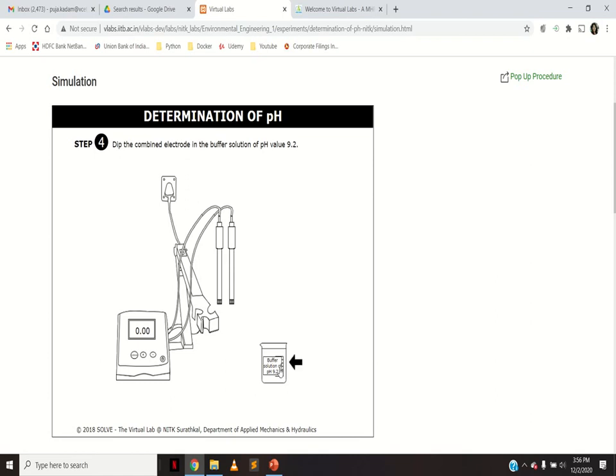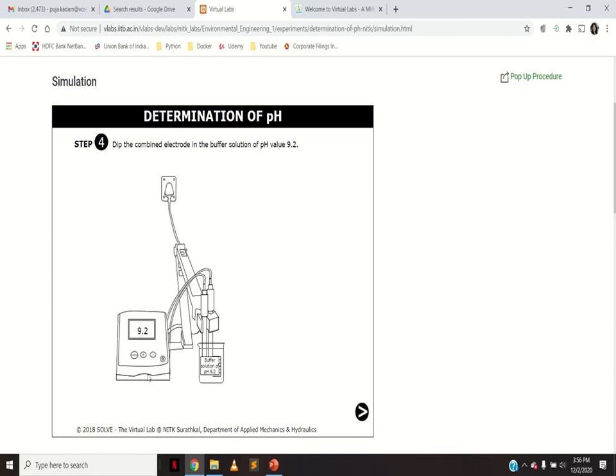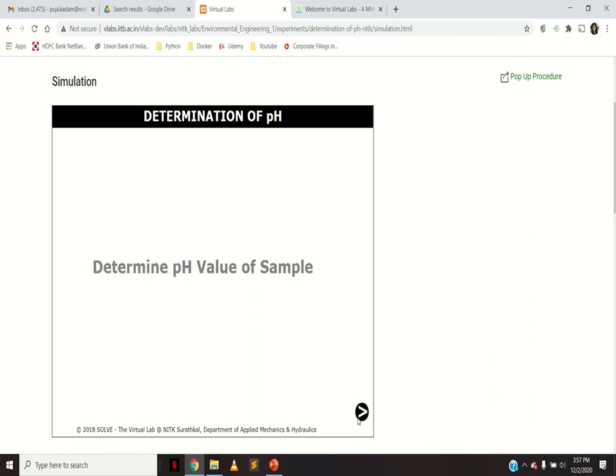You have a standard buffer solution of pH 9.2. Dip the electrodes into that buffer solution and calibrate until it reads 9.2. If the instrument is properly calibrated it will directly display 9.2; if not, rotate the knob or press the 9.2 button until the digital display shows 9.2. This way you calibrate your pH meter. When dipping in pH 4 buffer it gives 4.0, and when dipping in pH 9.2 buffer it gives 9.2 — confirming the instrument is calibrated.